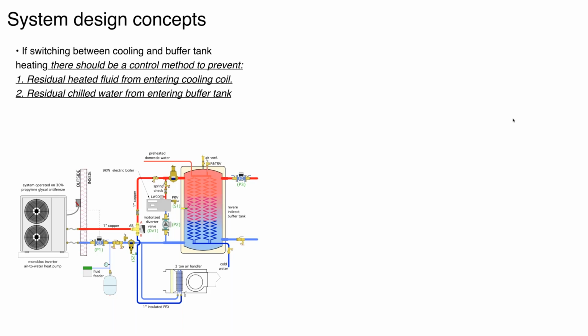If we just move the reverse or the motorized valve and we send, let's say, 3 or 4 gallons of 120 degree fluid into the cooling coil, imagine you're sitting there in a living room and it's a hot, sweltering day. And when the cooling comes back on, you get this blast of warm air for maybe a minute. Most people are not going to like that. They're going to say, why is the system blowing this slug of warm water, several times a day when cooling comes back on? So how do you deal with that?